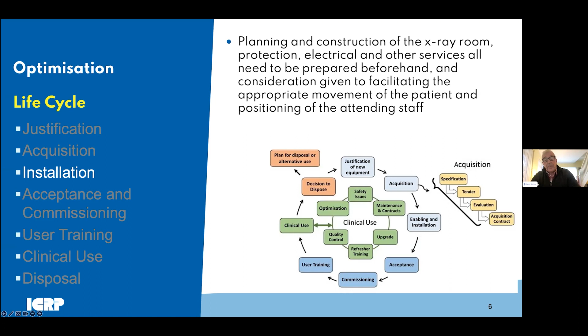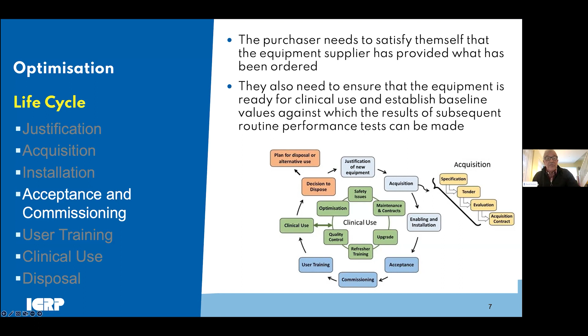And once the equipment's been installed, the next step is acceptance and commissioning. There is a lot that can be said and a lot has been said about both of these topics, but it's key that the team understand the difference between acceptance and commissioning. You need to satisfy yourself that the manufacturer or supplier has supplied what you ordered and that it meets the specification. This is called acceptance. You also need to establish baseline values that you will use for subsequent comparative testing, whether it be on a daily, weekly, monthly, or yearly basis. And this is commissioning. It's important that your plans allow sufficient time for both, and also for the resolution, of course, of any issues identified, especially during the acceptance phase.